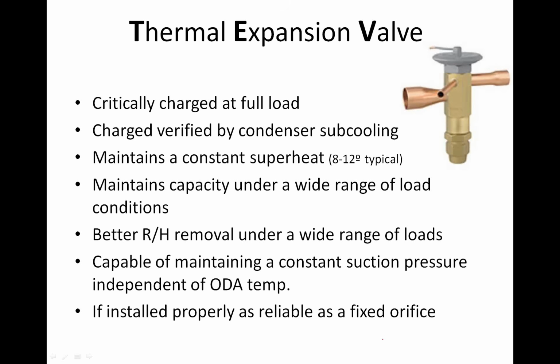So your total superheat is the superheat measured at the compressor inlet, right? And that's typically where we measure superheat when we're charging a fixed orifice system. Again, even though we're maintaining a constant evaporator superheat of 8 to 12, that could be anywhere from 12 to 20, 25 degrees of total superheat by the time it gets to the compressor.